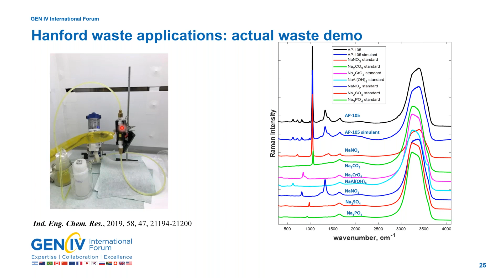The spectra of the AP105 waste is shown here as a function of sample number, which is essentially a time axis. We have the wave number, so we can see the water manifold here, or the hydroxide manifold here. We see the nitrate band over here. So we start the process where we have water initially in the cuvette flow loop. Then we transition over to AP105 waste and measure that. Now we can go ahead and then use our chemometric models and process this spectral data and turn that into concentration data based on the model that we employed. And this shows the concentration in the y-axis versus time through the process.